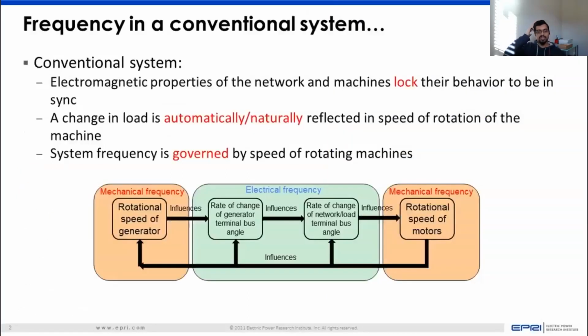Before we go further, just a recap of some of the theoretical aspects. This is something I'm sure a lot of you already know, but I find that it helps set the tone of the entire topic when we reflect on what frequency control is in a conventional system. In a conventional system, things are inherently linked because of the electromagnetic properties of the network and the machine. The rotational speed of the machine influences angle because of the electromagnetic link between the network and the machine, which in turn influences the change of angle on the load side, which in turn influences the speed of motors on the load end, especially if you have induction motors, more so if you have synchronous motors. All of this has an implicit feedback path that coordinates each of the elements based upon Lenz's law and Maxwell's laws that ripple through the network.